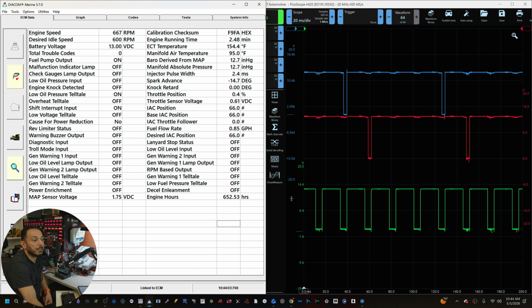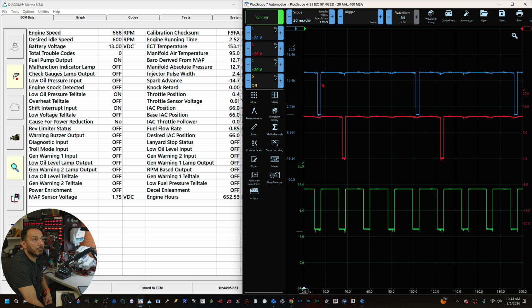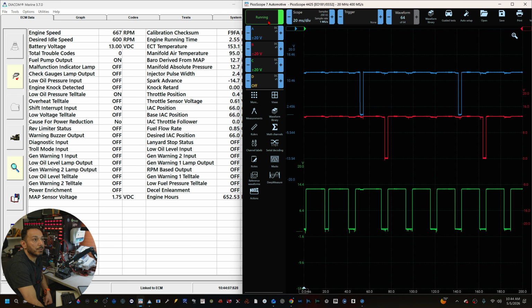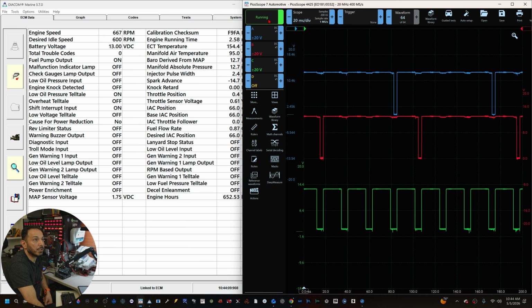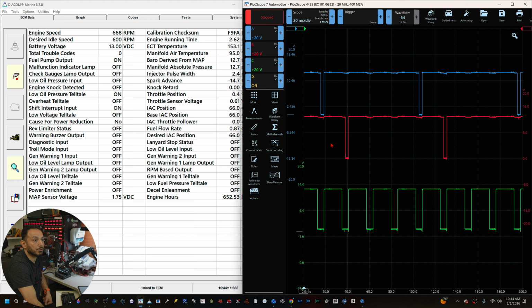But I don't expect that to happen, right? So I'm going to pause, because I can do that in the upper section. You see what it says run, and I'm going to pause that capture to see what we have here. So we should have in the blue channel in the upper section battery voltage, and we got 13.4 volts. And on the bottom, when the activation happens, we should be very close to ground, and we got 0.096. So that is perfectly pulling to ground.